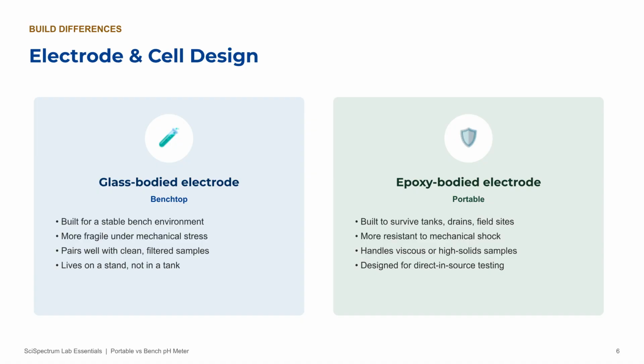Now let's talk about the electrode itself, because this matters more than people give it credit for. Benchtop electrodes are typically glass-bodied, built for a stable bench environment, but more fragile if you knock them around. Portable electrodes are usually epoxy-bodied, built to survive being dipped straight into a tank, a drain, or a field sample point. So if your samples are viscous, high in solids, or you're testing right at the source, say an ETP outlet, the electrode's build quality matters just as much as what's on the meter's display.